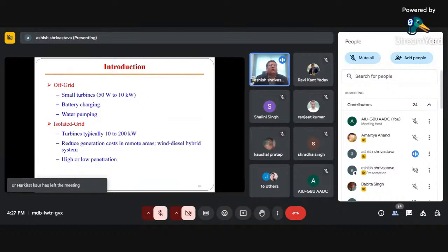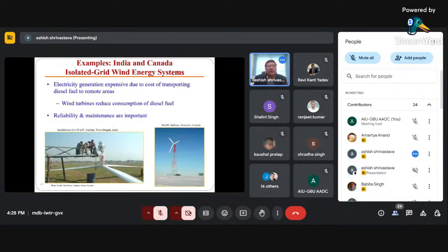If you talk about off-grid, well, small turbines of 50 watt to 10 kilowatt, you can use for battery charging. For water pumping also, you can use during off-grid. In an isolated grid, you can use turbines of 10 to 200 kilowatt, which can reduce generation cost in remote areas where you can use wind diesel as a hybrid system. And it can also be used at high to low penetration depending upon the availability of the wind. These are a few examples of isolated grid wind energy systems.